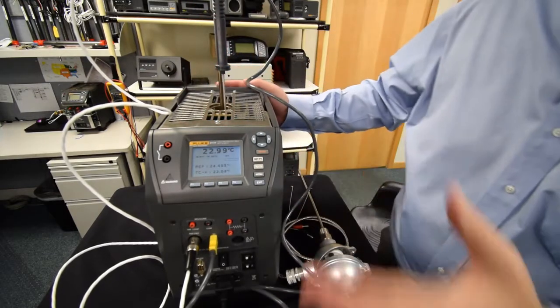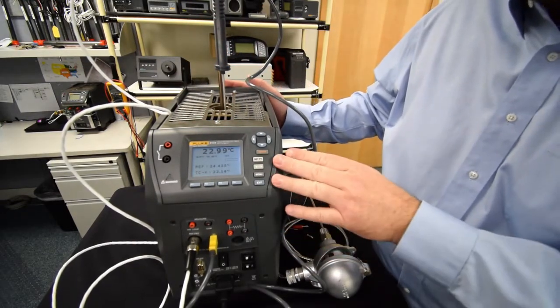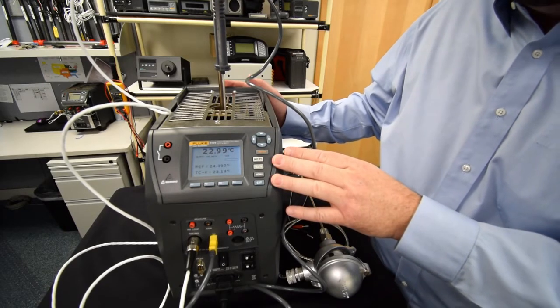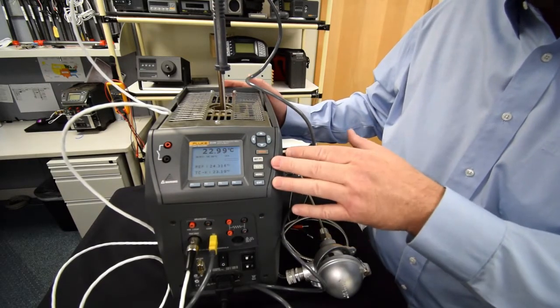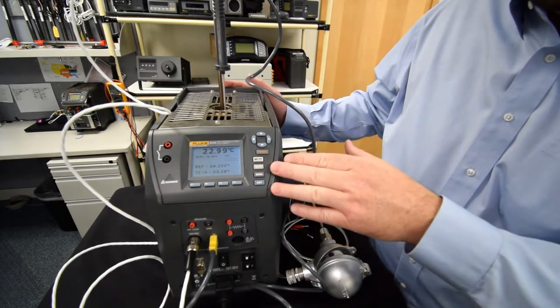And then we would be able to set the appropriate set points. This unit also has a ramp soak feature and can store some tests, very basic test setup. So it will ramp and soak and then store that data that's collected here.